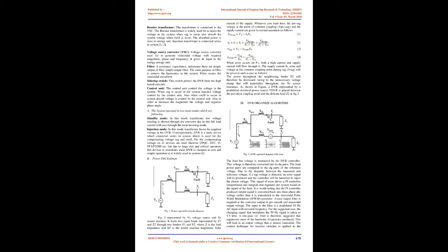Booster transformer. The transformer is connected to the VSC. The booster transformer is widely used to inject the voltage into the system when sag occurs, and also to absorb the system voltage when swell occurs. The absorbed power is stored in the storage unit. The injection transformer is connected in series in the system 1, 3. Voltage source converter, VSC. The voltage source converter is used to generate sinusoidal voltage with the required magnitude, phase, and frequency. It receives DC input from the energy storage unit.